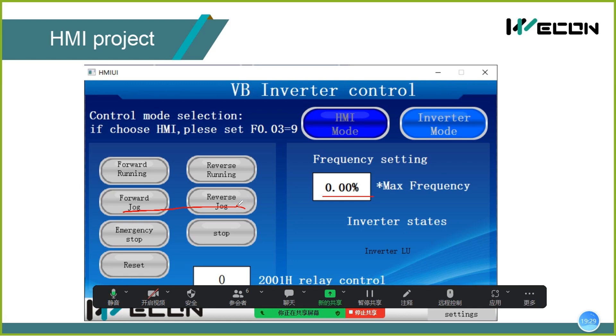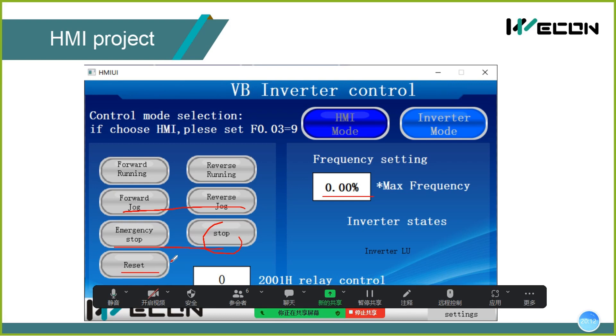These two buttons are point (jog) operation. You can set the jog frequency in the F8 group parameters. These two buttons are stop buttons. Emergency stop means the inverter will stop directly, while the deceleration stop follows the configured stopping method.